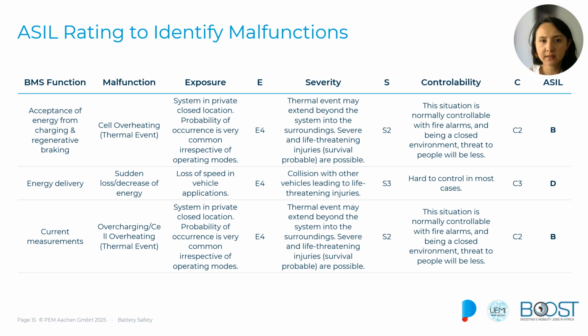All of these, and the different ASIL levels of the BMS functions, for instance, will have important implications in the BMS. First, it will reflect the complexity of the design. If we have features with ASIL-D requirements, for example, this will call for exhaustive design reviews, fault-tolerant measures, and rigorous testing, to guarantee an extremely low likelihood of dangerous failures.